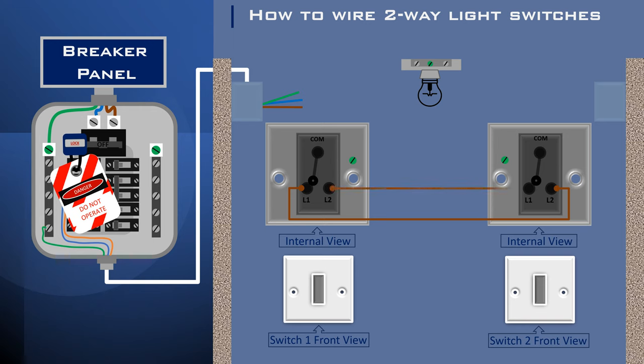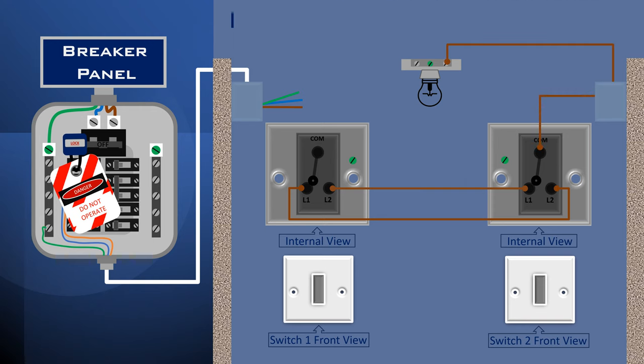At the light fixture location, connect the brown wire from the second switch common terminal to the live terminal of the light fixture. At the first switch location, connect the live brown wire coming from the power supply to the common terminal. Connect the blue wire coming from the same power supply to the neutral terminal of the light fixture.